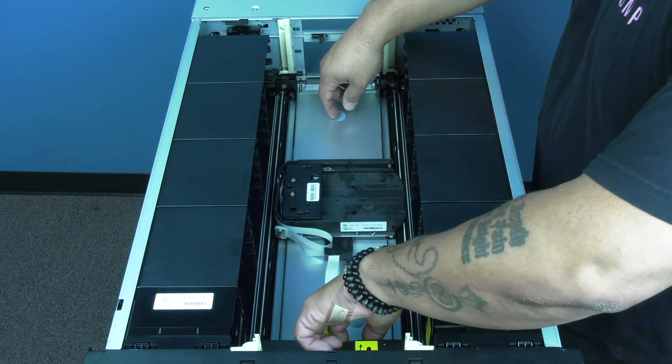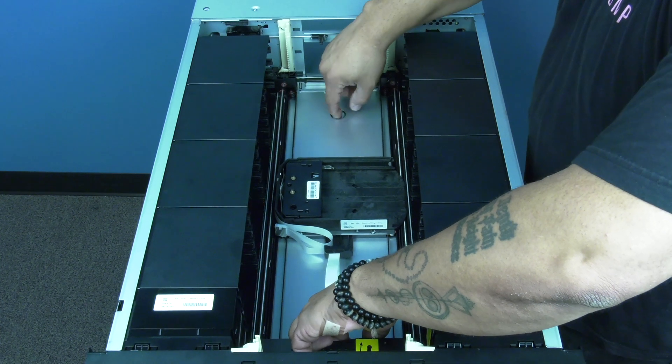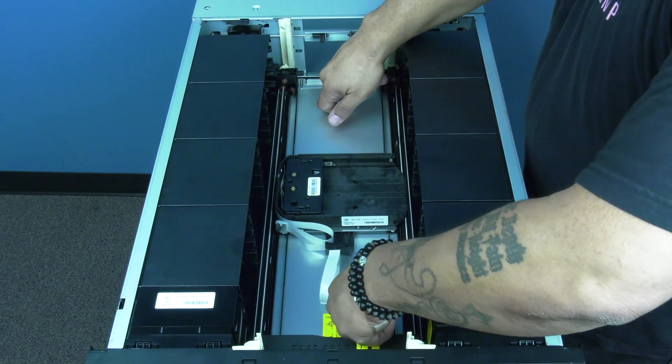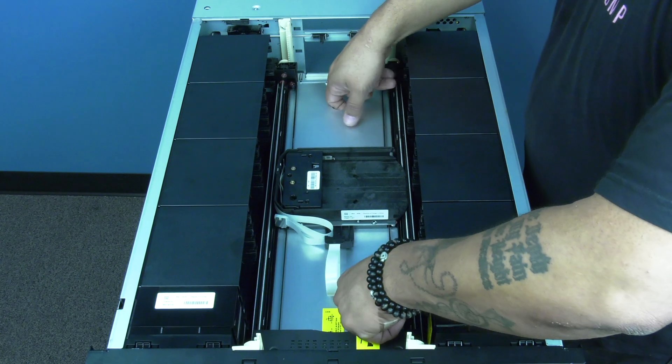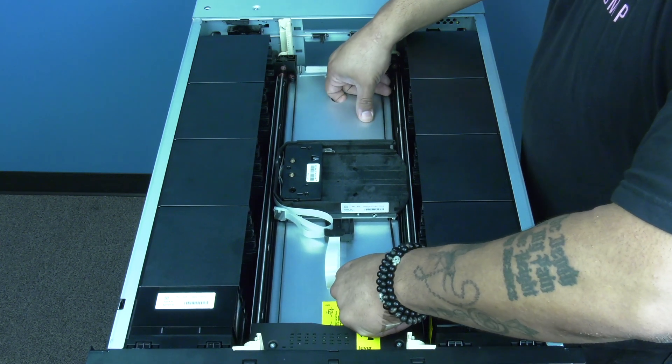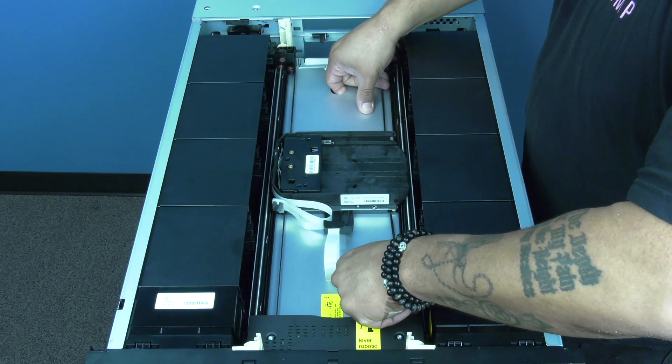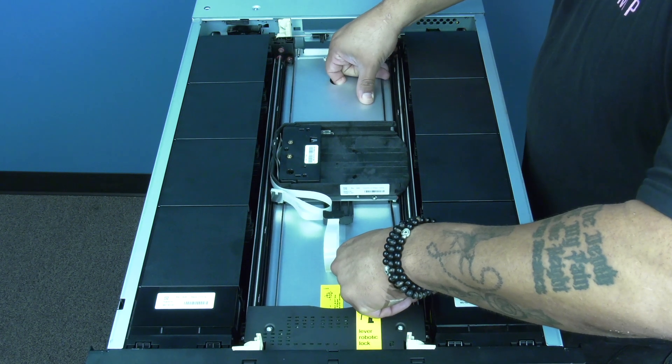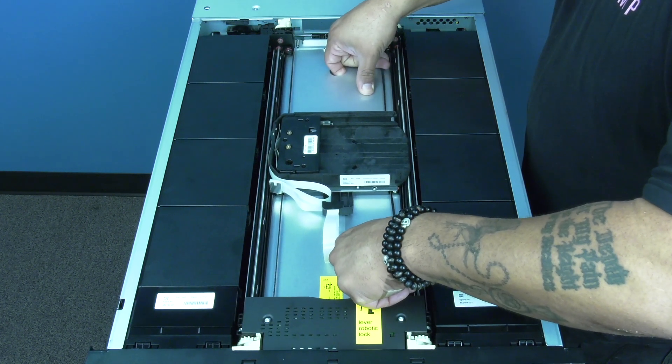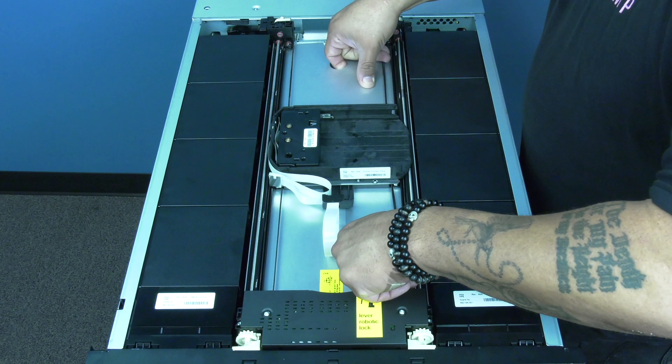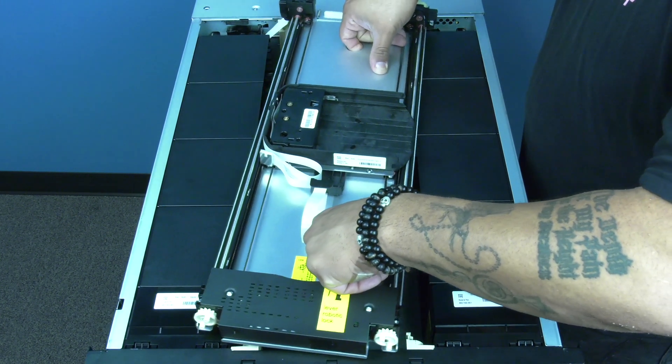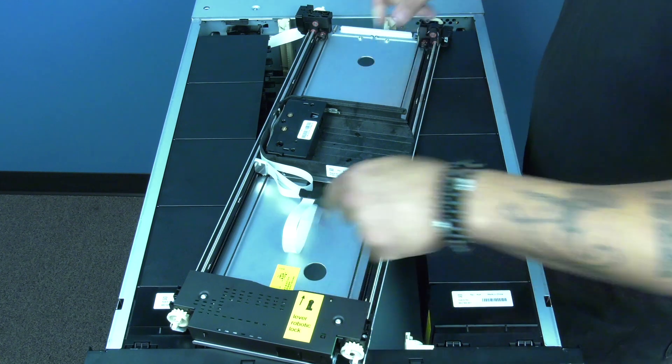Put your fingers in the large holes on either side of the robotic hand and slowly lift the robot up the tracks. It will move slowly and offer some resistance. Please do not pull it up with a fast or sudden motion as this may damage the picker. Once you have the picker at the top of the tracks, you can carefully pull it out and set it on the top of the right side of the module. Be careful not to damage the picker cable as it will still be attached.